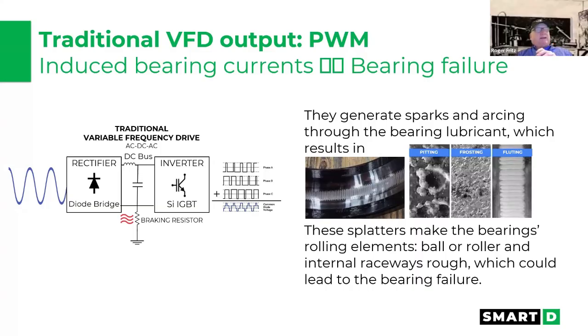There's a fellow in France that I've met who has done a study of 900 motor applications with and without VFDs, and has found that the failure rate of the drives with VFDs on them is roughly 40% higher than it is with just going straight across the line. So you've got to look at, well, what is the true advantage of putting the frequency on? Yeah, we save a lot of power because we're reducing the loads to the item.